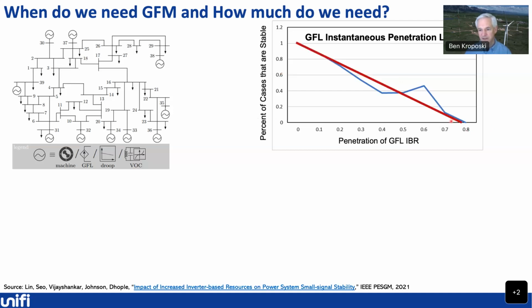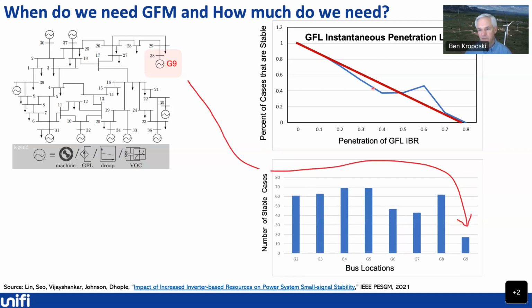You can see basically there's a line here that's going down, and as you would expect, as you had less of these grid following inverters, you had a more stable system. As you increase the grid following levels, you had a less stable system. Of course, there's some little pieces here that go outside that just nominal straight line. And if we take a closer look at what's causing these particular systems, you end up finding that those are mostly caused by the fact that your buses that are furthest away from the rest of the generation sources, in this case bus 38 or generator 9, actually had the least number of stable cases. So what this ends up showing you is that in general, you get this decline in stability if you're only using grid following inverters.